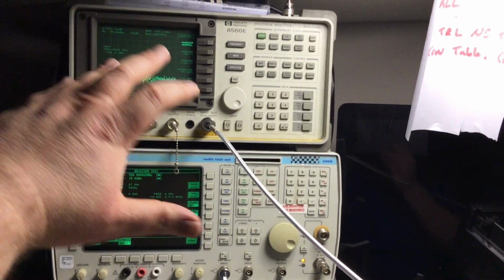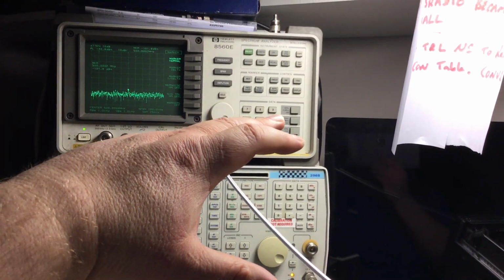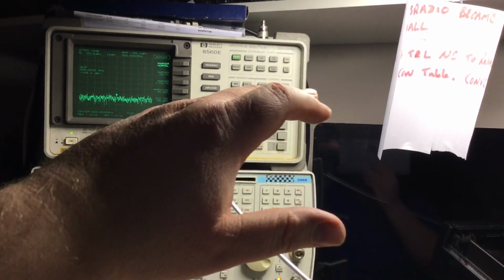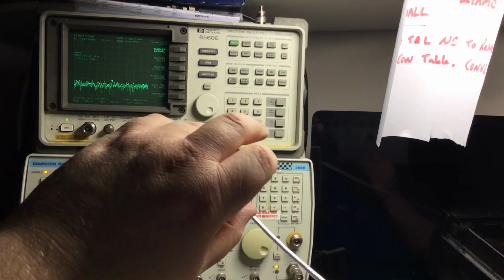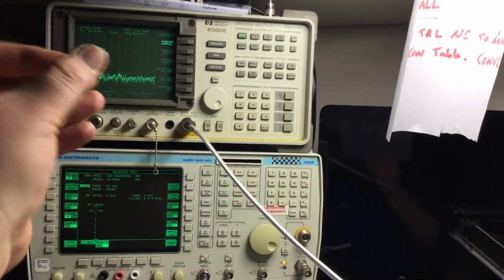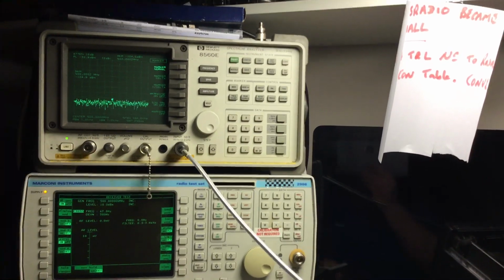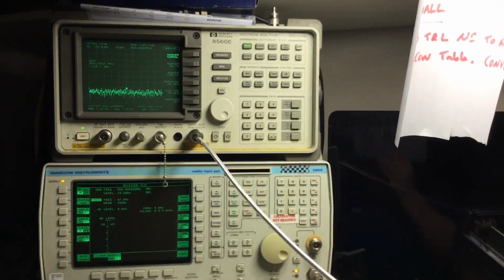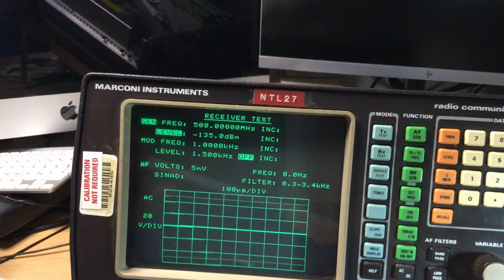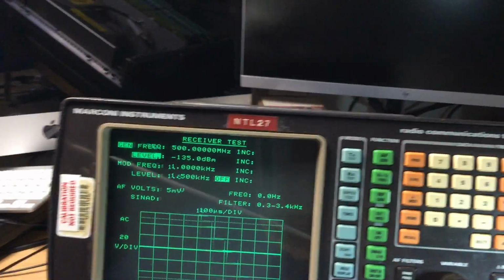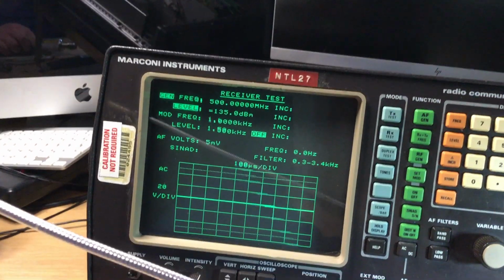Even if I go into setting this up better, which I can do, to try and display 2 dB steps instead of 10 dB, and I alter the resolution bandwidth and dynamic resolution, and I change all that to the finest minute detail in order to pull out the most microscopic signals, it will still not be able to read down to that level, negative 135 dBm. So this is why we then need to go to the next stage.